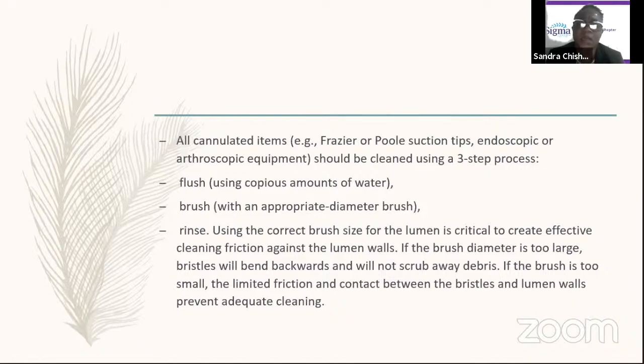the debris and organic or inorganic items from the cannula. Using the correct brush size is critical, because you don't want a brush size that is too large. If it is too large, the bristles will bend and it will not scrub away the debris. Or if the bristles are too small, the friction will not be adequate to remove the debris from the lumen of the cannula. And the next step is rinsing. So you flush, you brush, then you rinse.